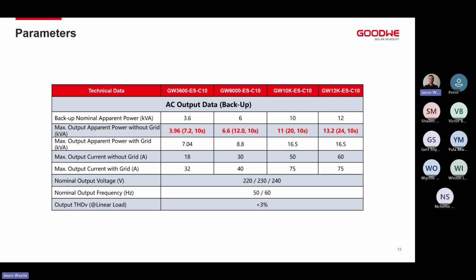The same as when it comes to our overloading capacity on the inverters, all of them can do 200% for 10 seconds. So on the 12 kilowatt unit, we can run 24 kilowatts of output for 10 seconds before we get an overload. And where this happens or where this comes from is on the DC capacitors that are built into the inverter, not necessarily through the batteries itself. So you don't have to worry about batteries being over discharged or overcharged. The inverter will never harm the battery in that way.